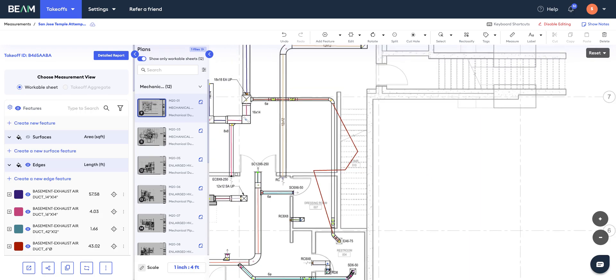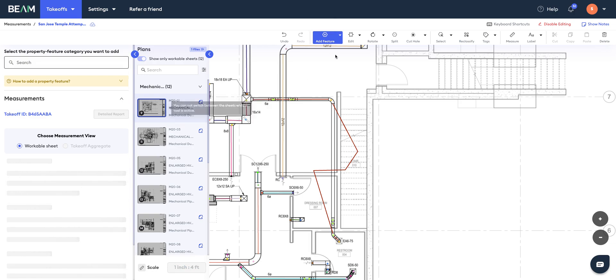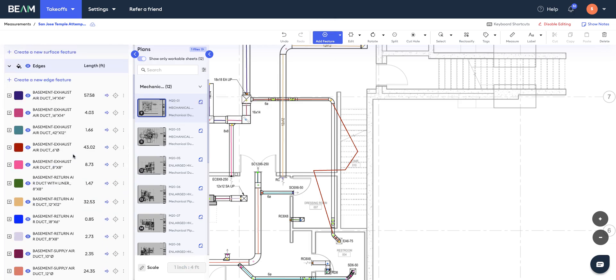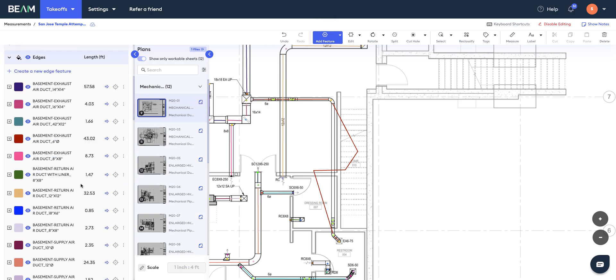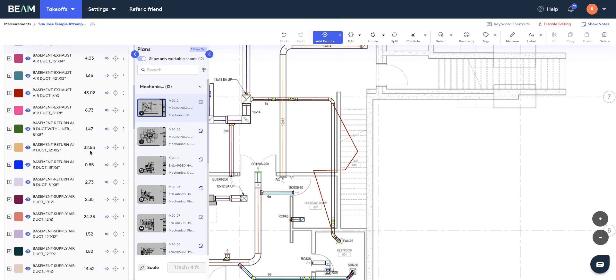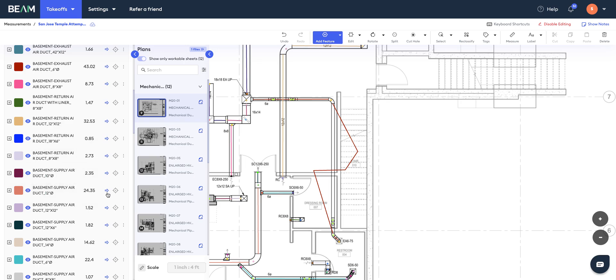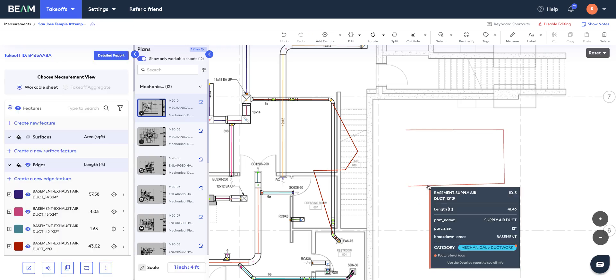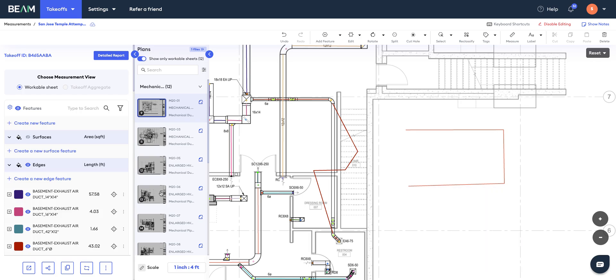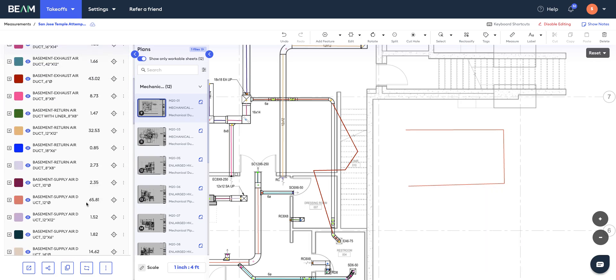Let's say now you want to draw a new duct length yourself. For that, you need to click on this add feature button. Once you do that, you can go and select whichever feature you want to add. Let's say I want to draw a new length of this basement supply air duct, which is 12 inches in diameter. I click on this arrow and then I can trace out that length, double-click to finish, hit escape, and you'll see that the software has drawn this takeoff for you and added those quantities to this category in real time.